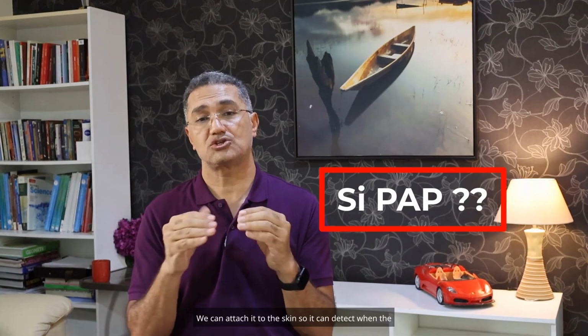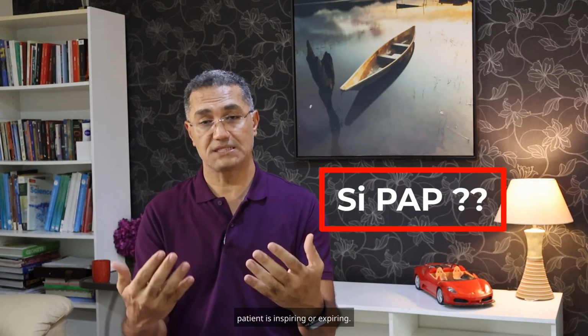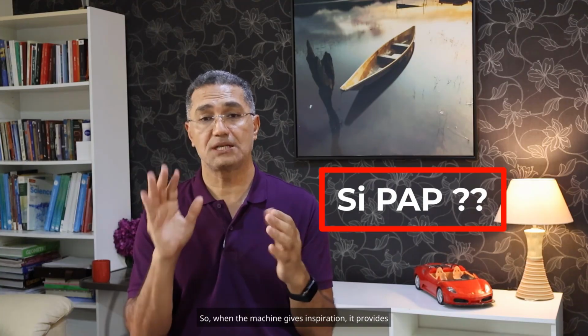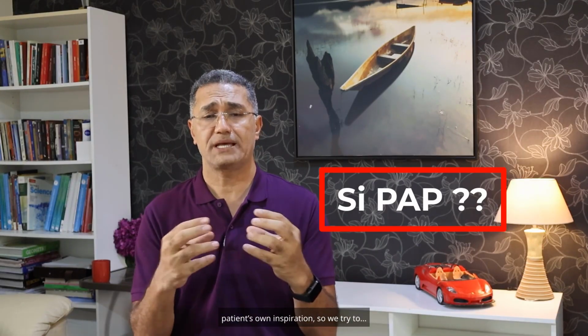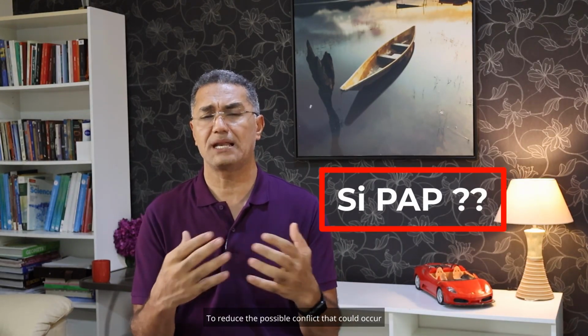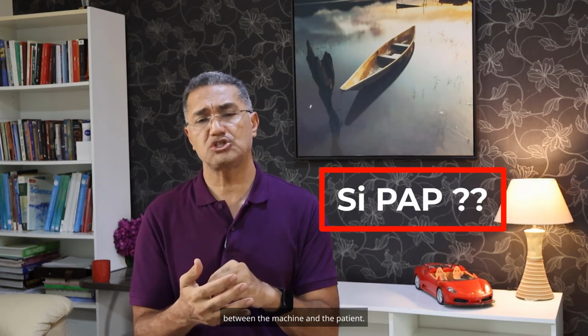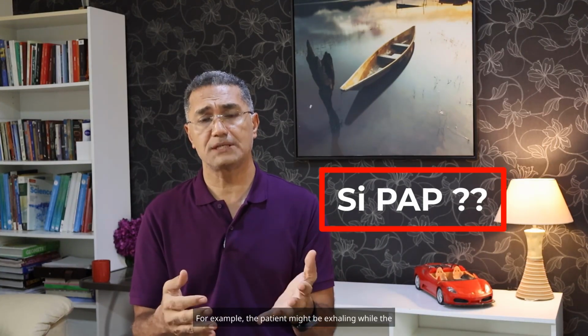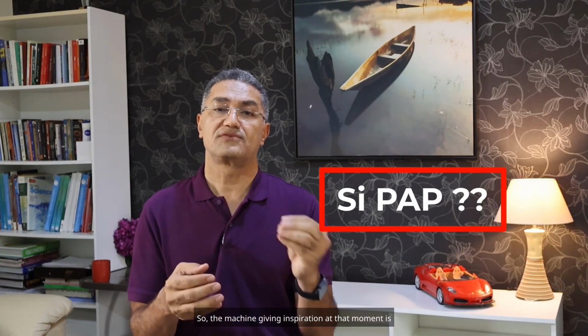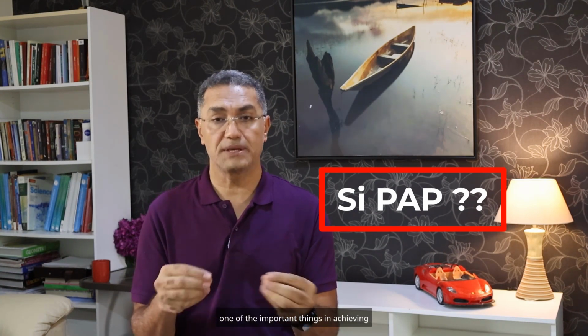We can attach it to the skin so it can detect when the patient is inspiring or expiring. So when the machine gives inspiration, it provides synchronized inspiration, meaning it matches the patient's own inspiration. So we try to reduce the possible conflict that could occur between the machine and the patient. For example, the patient might be exhaling while the machine is giving inspiration. Achieving synchronization avoids that, and that's why it's called synchronization, Synchronized Inspiratory Positive Airway Pressure.